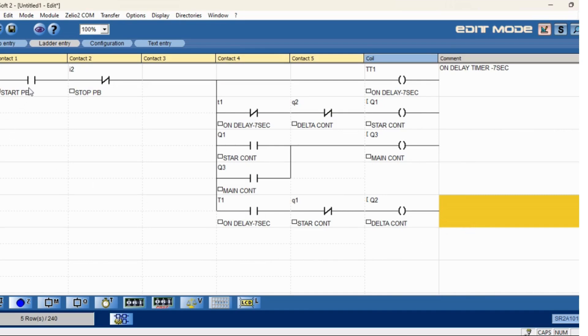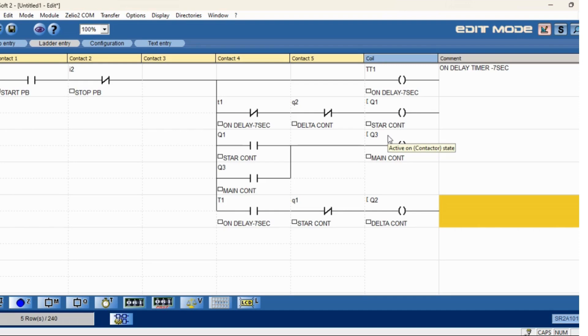When you enable the start command, the timer will be activated, and parallelly the star contactor and main contactor will be activated. After the preset time, it has to change into delta, so the star contactor immediately has to be stopped. This is the logic of star and delta. Now we will check in simulation.